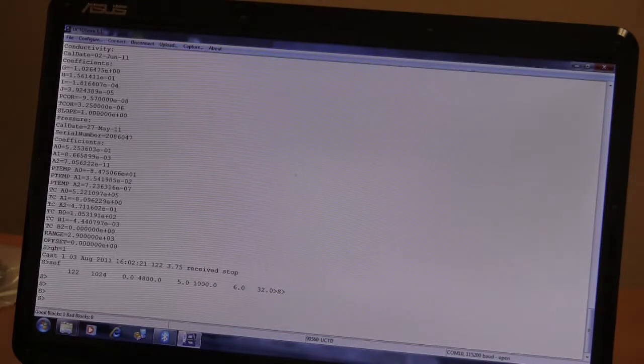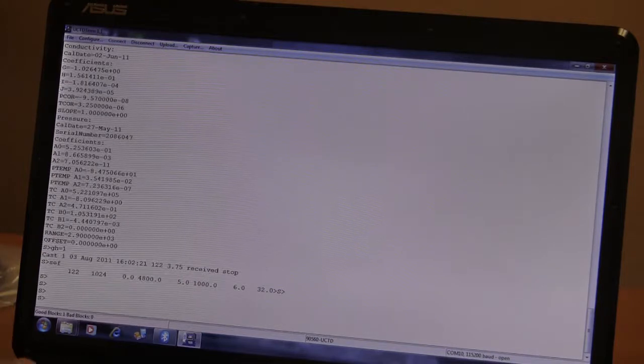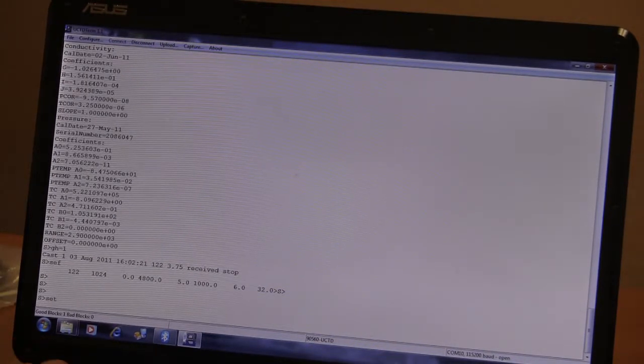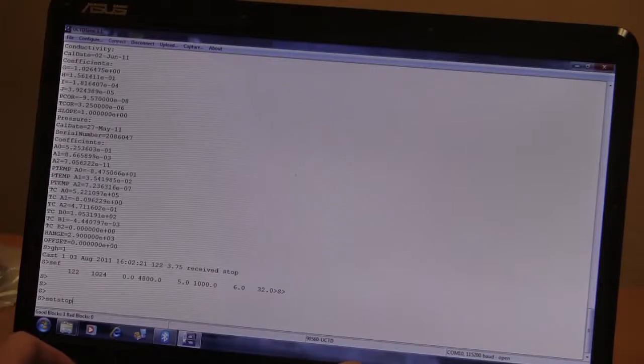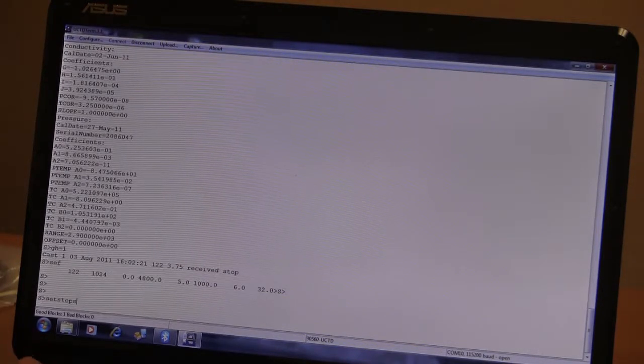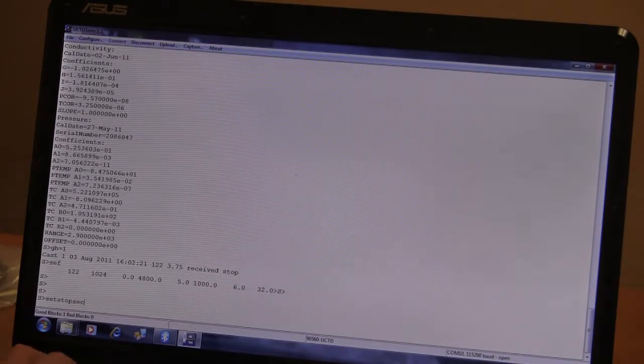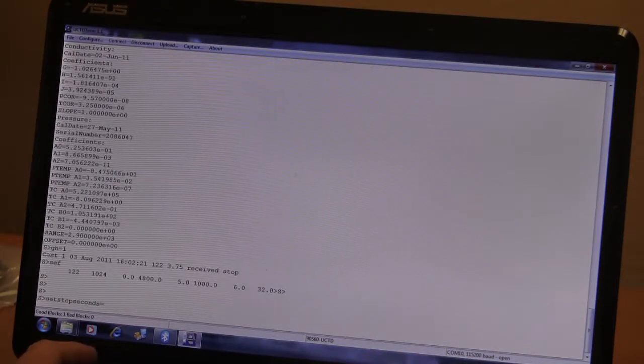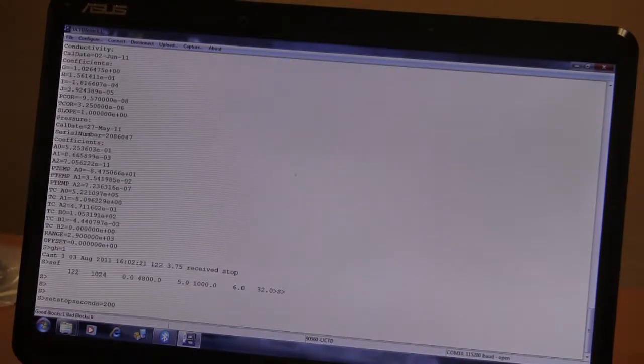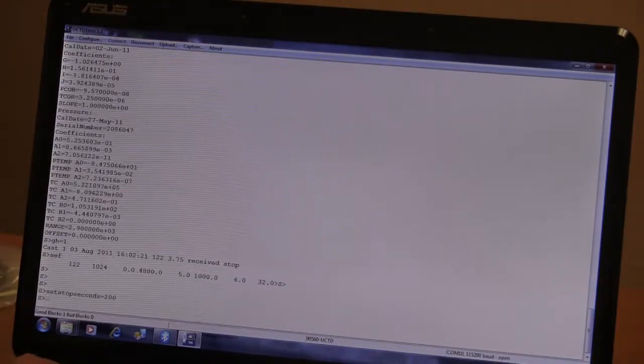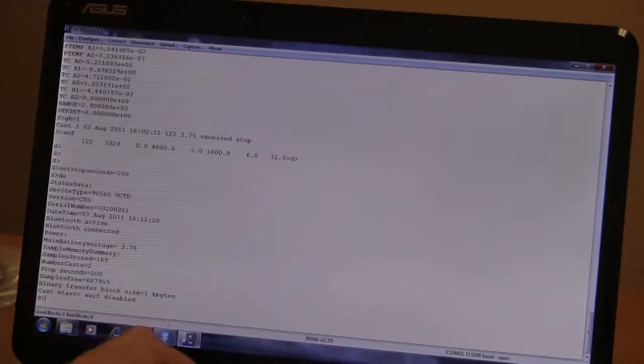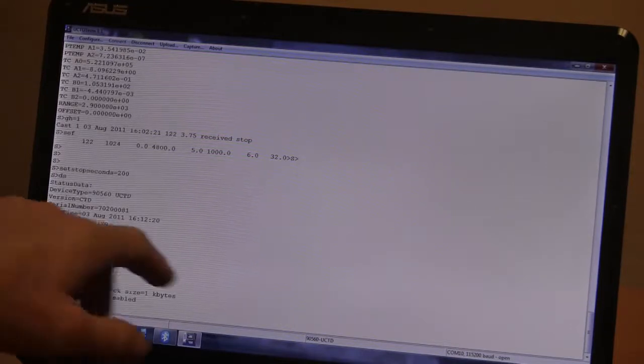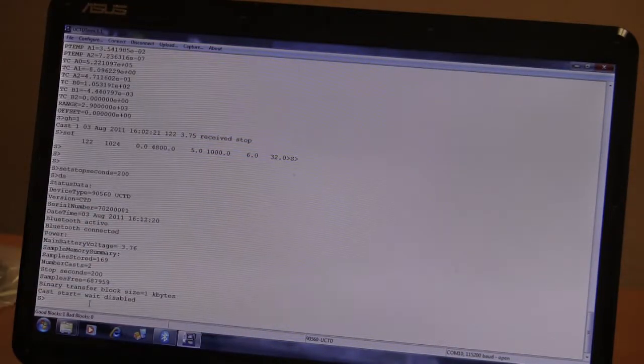A few other things you want to check: if you want to change the acquisition period, you issue the command set stop seconds. Now you can change it to 200 seconds for instance. If you look at the status, it's reflected in the fact that stop seconds are now 200. So whenever you pull the magnetic plug, it's now going to record for 200 seconds.